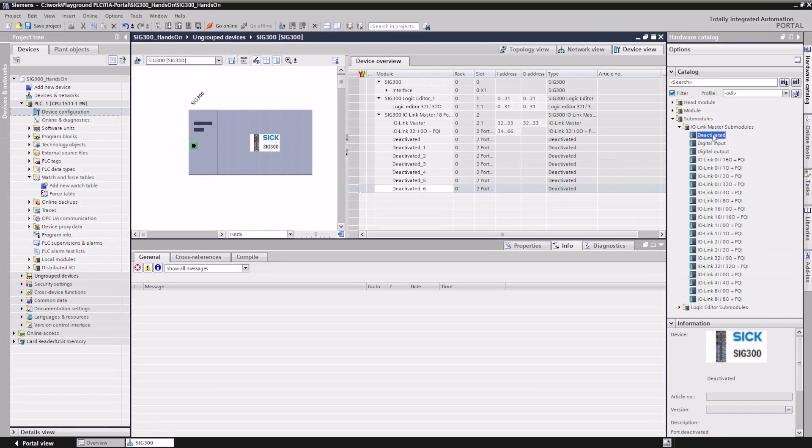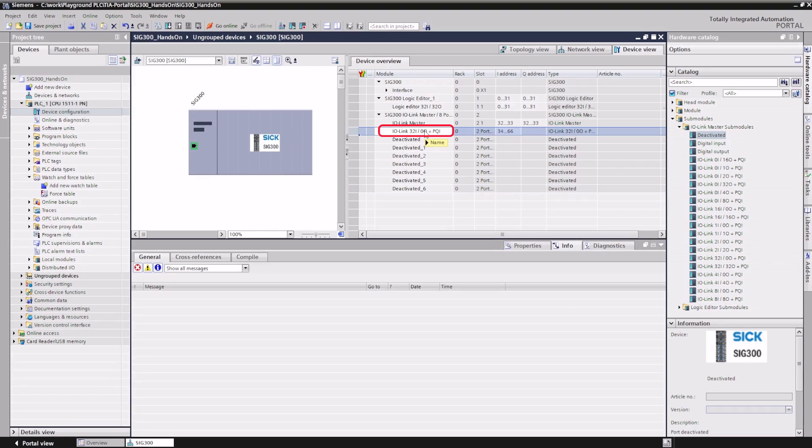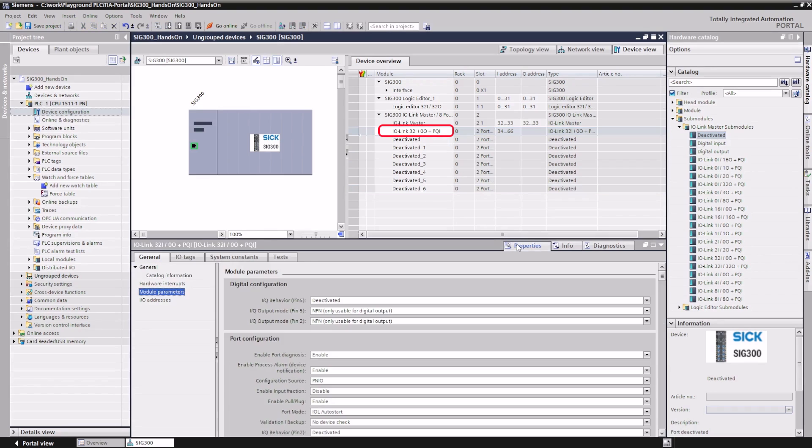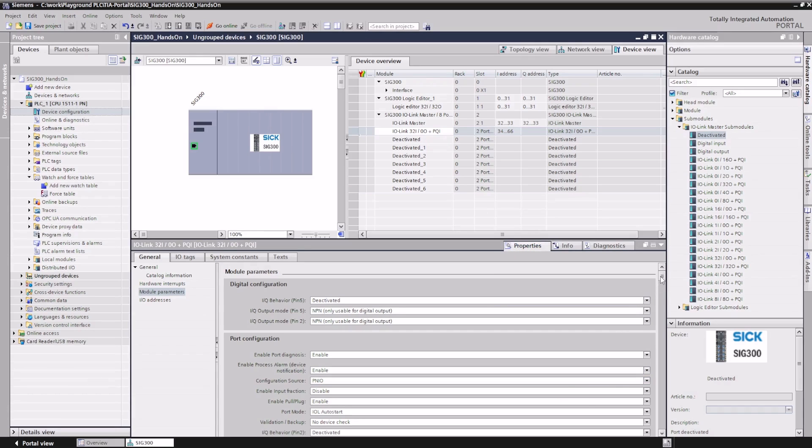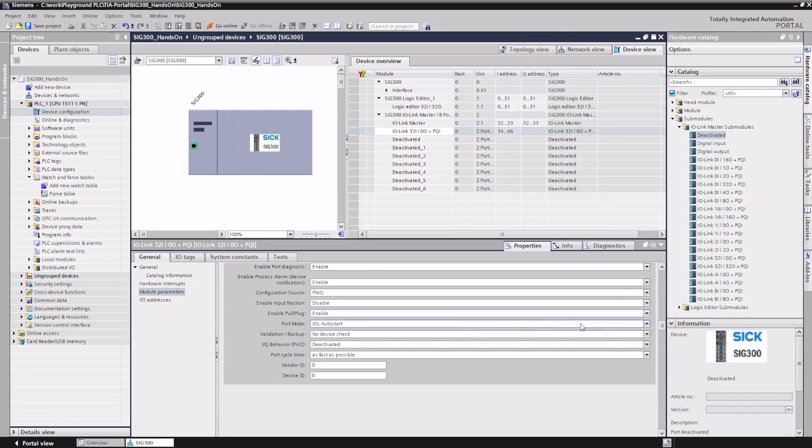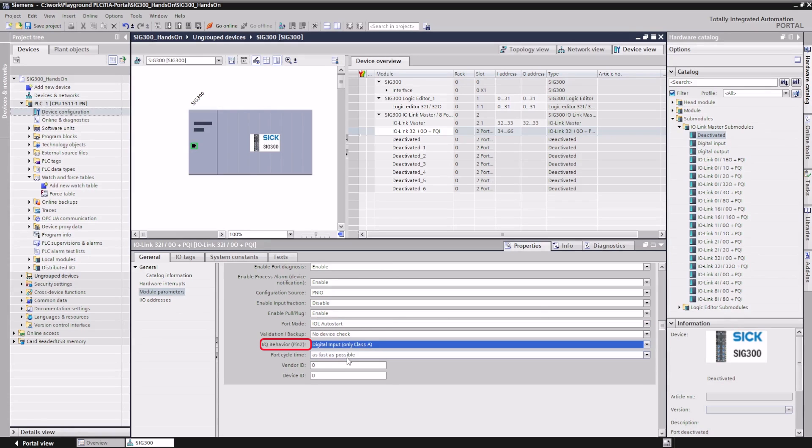The behavior of the master ports during the startup phase can be configured in the module parameters. Select your master port and open its properties. Among other things, the behavior of the additional PIN2 can be defined here. In this example, we configure PIN2 as a digital input. Depending on the sensor configuration, a digital signal is now transmitted from the IO-Link device to the input address of the IO-Link master sub-module, which can be used in the application program.